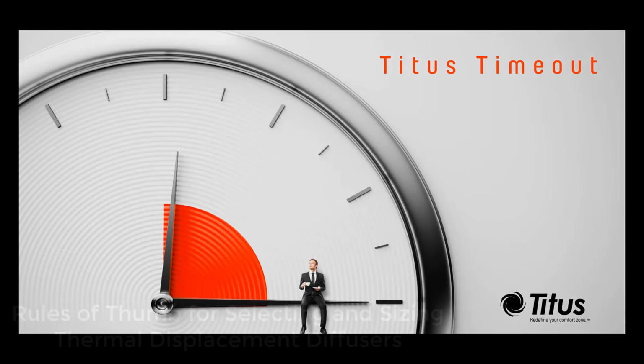I'm Ken Loudermilk, and this episode will be focused on rules of thumb for selecting and sizing thermal displacement diffusers. Thermal displacement diffusers are typically located in a low sidewall or floor location. They discharge cool air at very low velocities and rely on negative buoyancy of the discharge airstream to cause it to drop to the floor and move away from the outlet in a manner similar to a liquid spill.